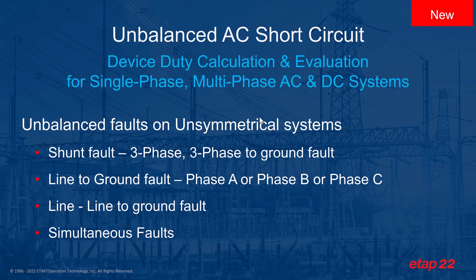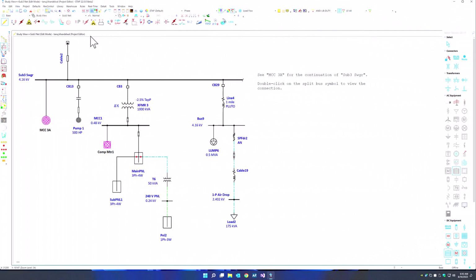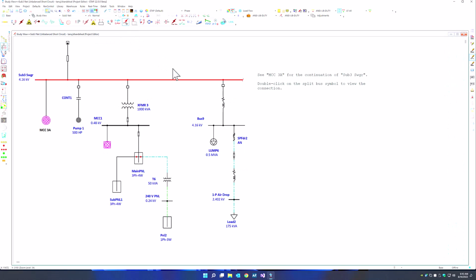These unbalanced faults can include shunt faults, line to ground faults, as well as simultaneous faults. The unbalanced fault on unsymmetrical systems, especially line to ground, can be applied from phase A, phase B, or phase C to ground, because each phase, based on the nature of an unsymmetrical system, can be completely unbalanced. So let's see this unbalanced short circuit module very quickly in action. We can simply switch over to our unbalanced short circuit mode and run our simulation.